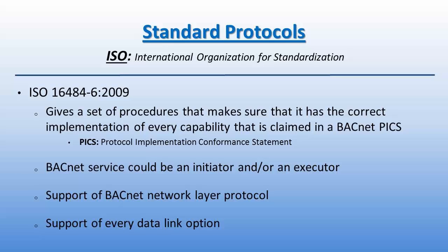PICS means Protocol Implementation Conformance Statement. A service in BACnet has to be claimed as an initiator, executor, or both. After being claimed, it supports every BACnet object type, which includes both required properties and optional properties. It also supports the network layer, data link option, and every claimed special functionality of a device.